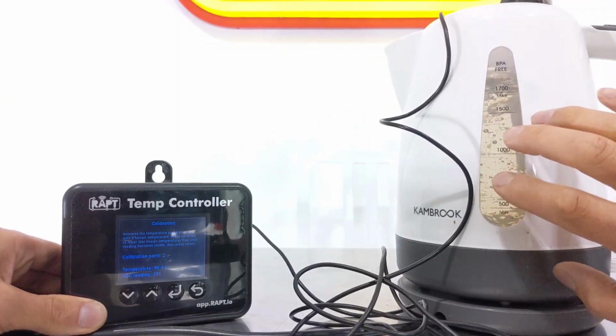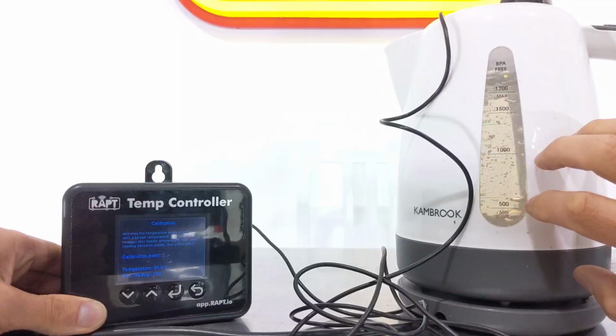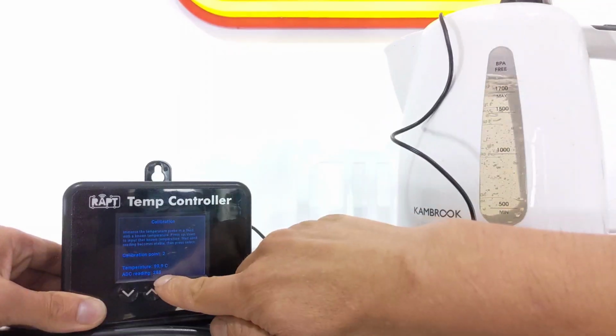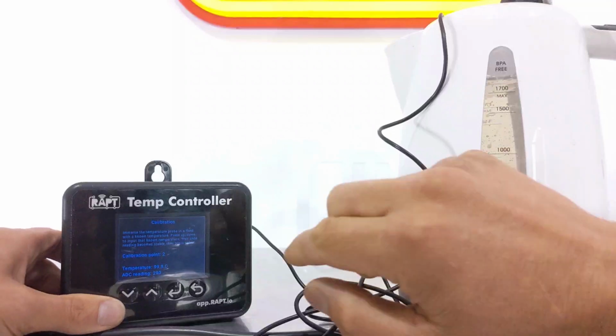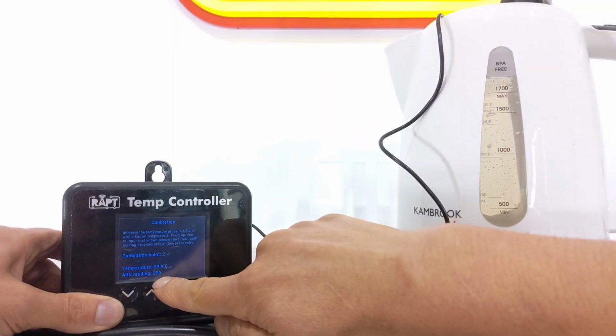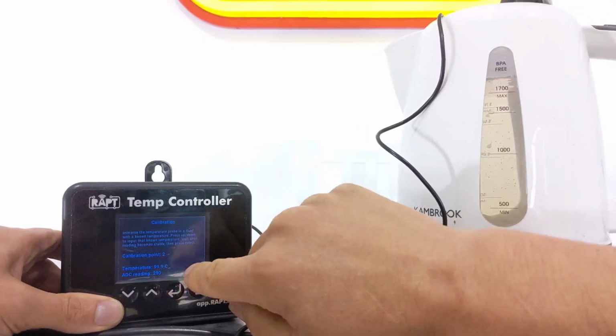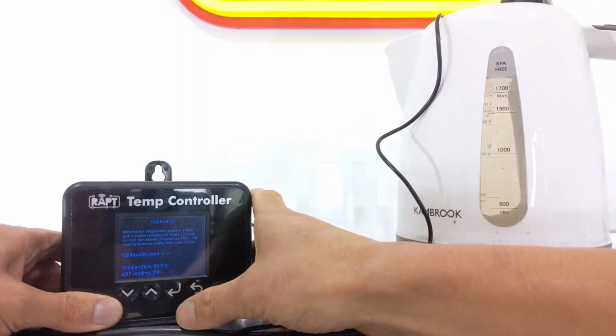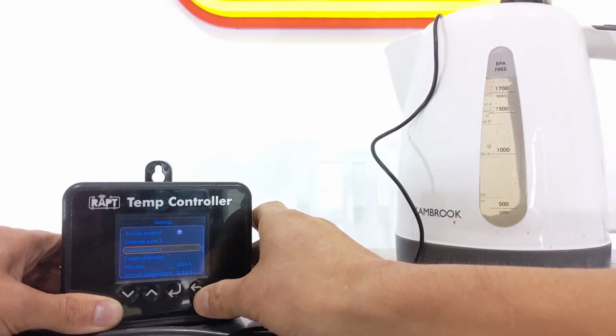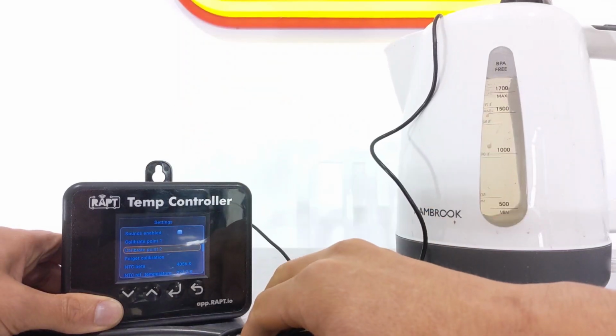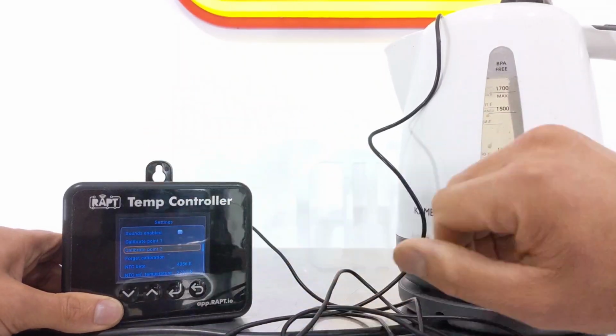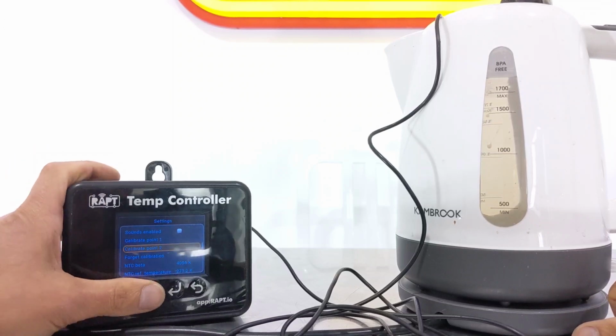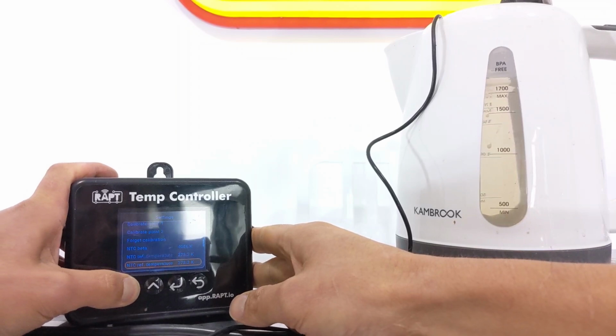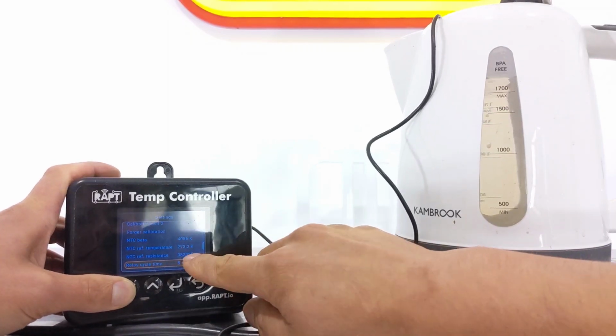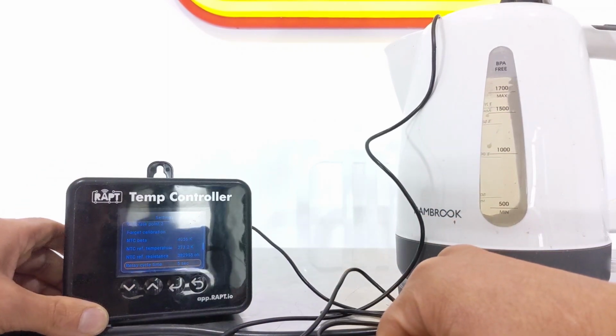Okay, that's great. You can see that I've definitely hit a boil here, but more importantly, my ADC reading has really started to plateau. As you can see, it's 290 or 289, pretty much bang on, and it's sort of hovering around there. So I'm going to hit enter now and save that point. And now I've finished the 2-point calibration. So that's all you have to do. It's really straightforward. Once you've got that in there, it'll automatically calculate these NTC figures for you. As you can see, these have now changed and it's redone that calculation.